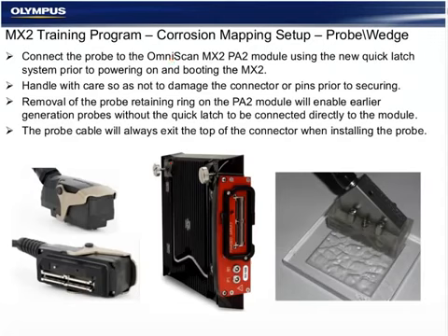The instrument module we're going to be using, and that was used to acquire the data today, is a new PA2 module designed to be used with MX2. It has a slightly different connector, a simultaneous LEMO UT board with the phased array, and this application requires a single group with one probe, so it can be done with any number of modules. The minimum requirement would be a 16:64 or up.